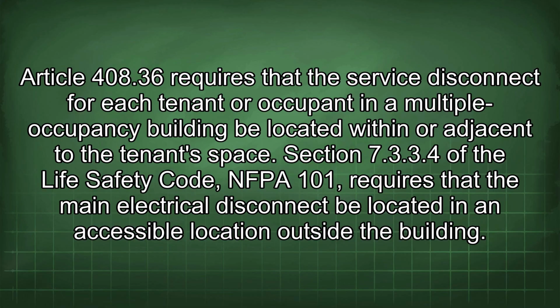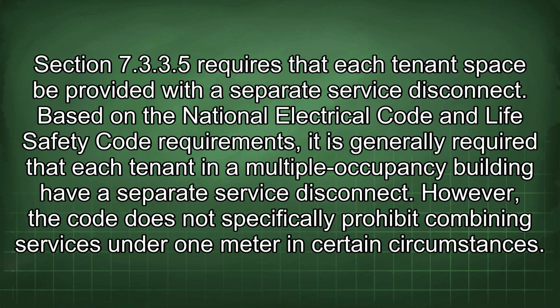Section 7.3.3.4 of the Life Safety Code, NFPA 101, requires that the main electrical disconnect be located in an accessible location outside the building. Section 7.3.3.5 requires that each tenant space be provided with a separate service disconnect. Based on the National Electrical Code and Life Safety Code requirements, it is generally required that each tenant in a multiple occupancy building have a separate service disconnect.